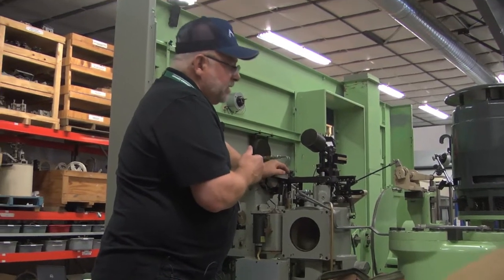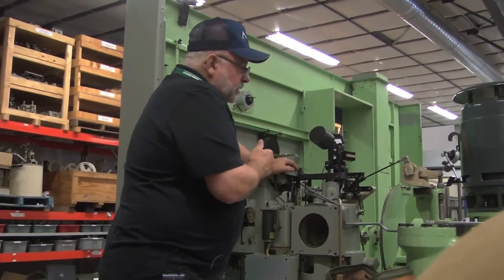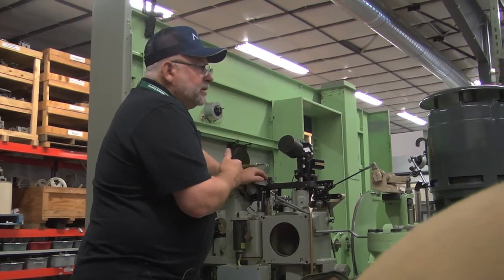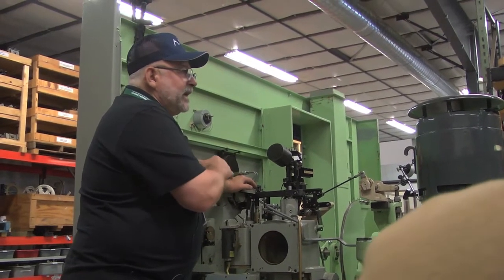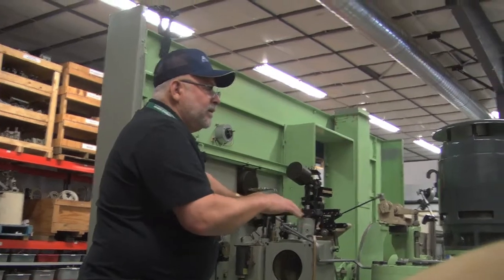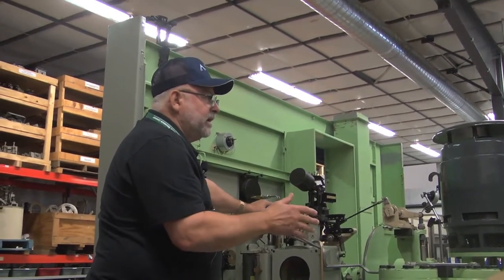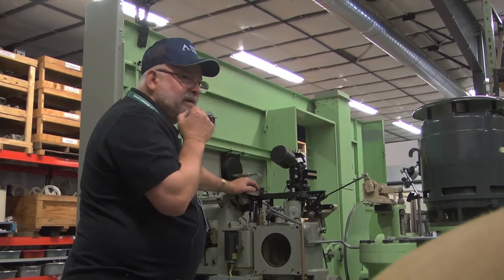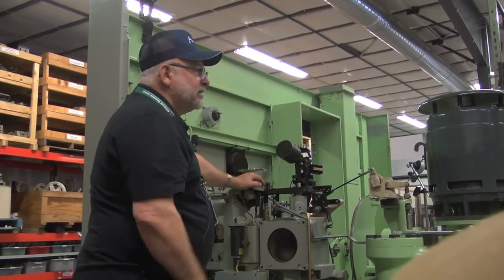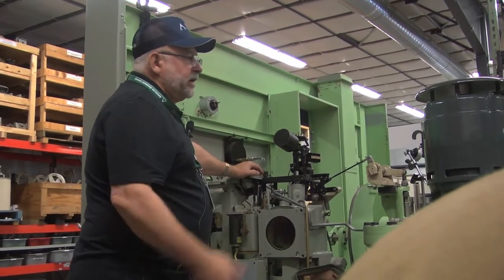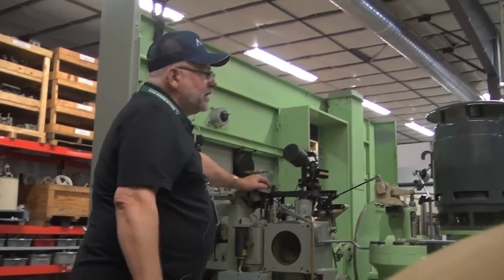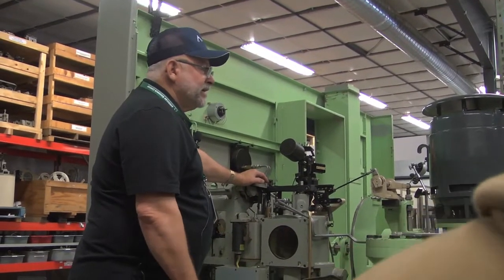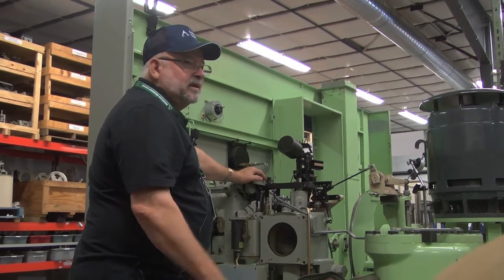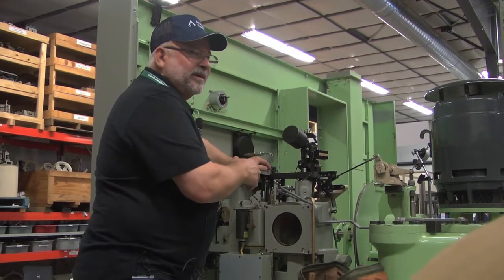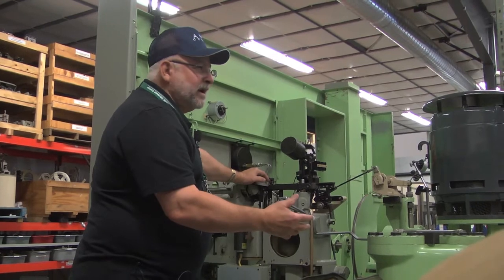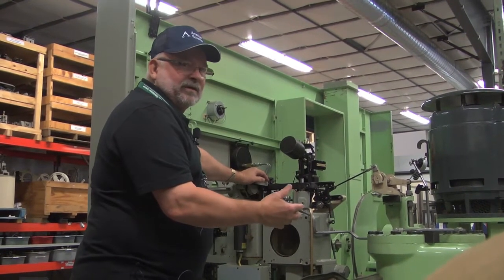I did a couple classes in Wyoming, Glendo and Boysen, and they had a guy that came out, and they did all theirs. It was a traveling crew that I was training, and they never had seen the units run because they had like 6 months outages. They just delivered water down the Wind River at Boysen, and at Glendo they just drained the lake at the end, and then they shut it down. To me, I'd hate to see that if I was working on a governor and I didn't get a chance to run it afterwards. I have a bad feeling.